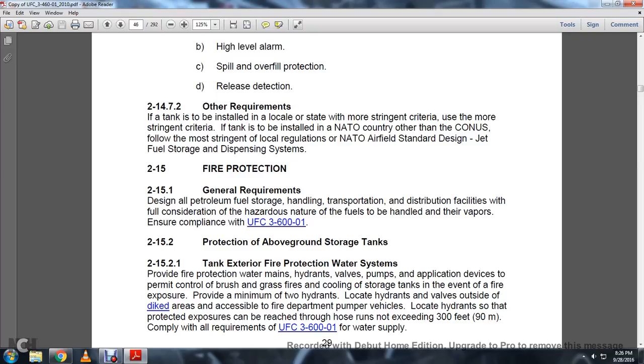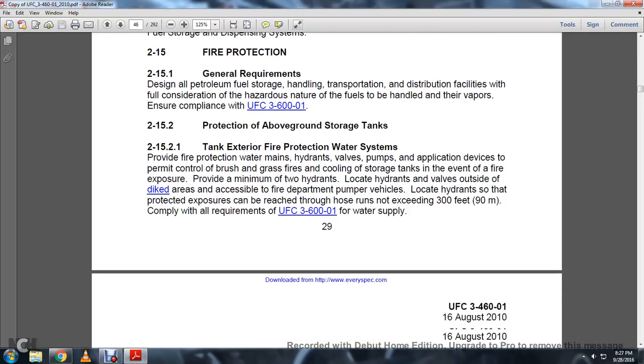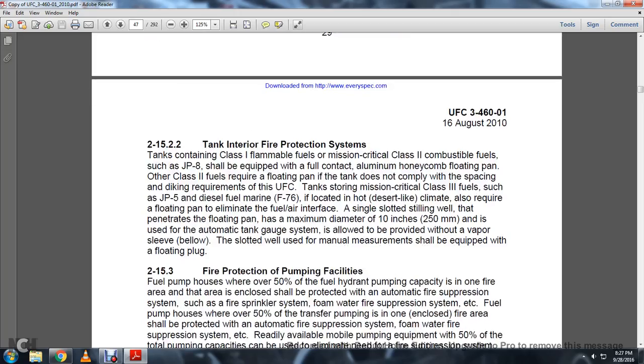Tanks require a fire protection water system. Provide fire protection water mains, hydrants, valves, pumps, application devices, to permit control of brush, grass fires, and cooling of the storage in the event of exposure. Provide a minimum of 2 hydrants located outside of the dike areas, accessible to the fire department pumper vehicles, so that the protected exposures can be reached through a hose run not exceeding 300 feet, to comply with all the requirements of UFC 3-600-01 water supply.